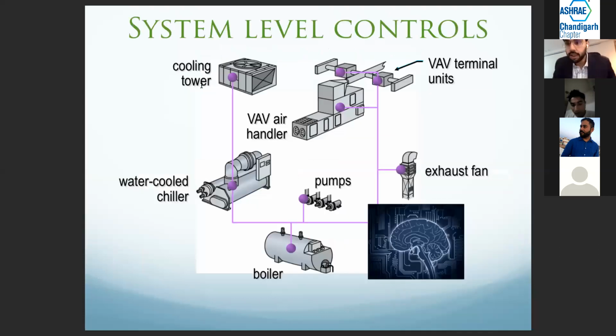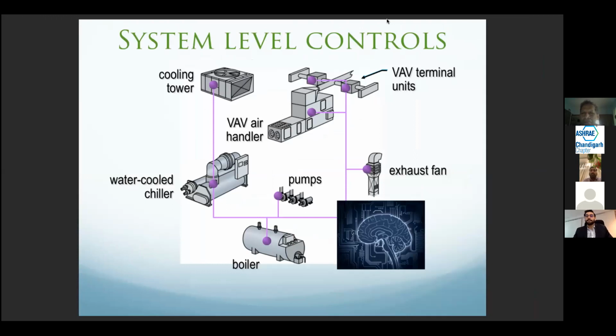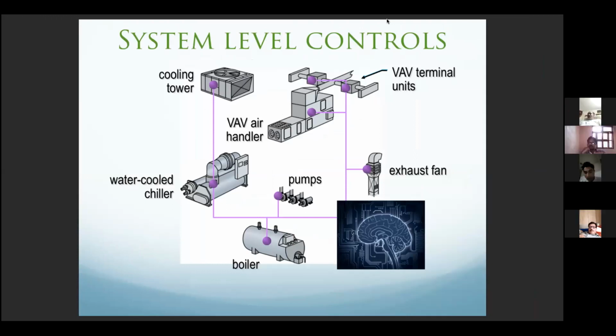So again, now system level controls. We talked about unit level controls, where the cooling tower may have a controller, the chiller will have a controller, the boiler will have a controller, and all the other equipment will have a controller. But at the end of the day, it's great that we have all these standalone controls, but we need everything to work together as one system. That is why we need the system level controls, to make sure everything talks together. This is where the logic resides. This is the brain of the system. This is where you typically have the graphics, programming, customized programming, anything of that sort.